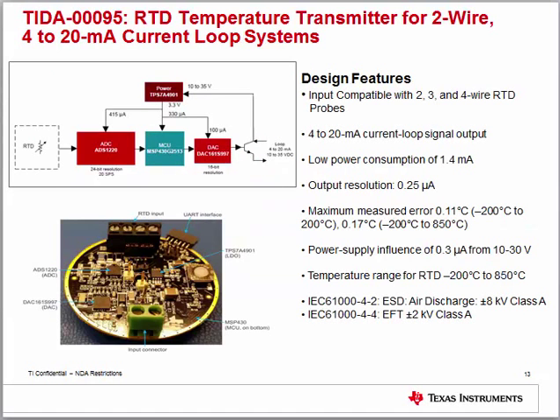This comprehensive design measures and processes temperature signals from 2-wire, 3-wire, and 4-wire RTDs and outputs a 4-20mA current loop signal corresponding to the processed temperature. Salient features include multi-wire probe input capability, very low power consumption, and fine resolution. The reference design has been tested for compliance with IEC-level ESD and EFT tests, helping avoid PCB iterations and reducing time to market. The design targets process measurement in factory automation, field transmitters, and building automation.